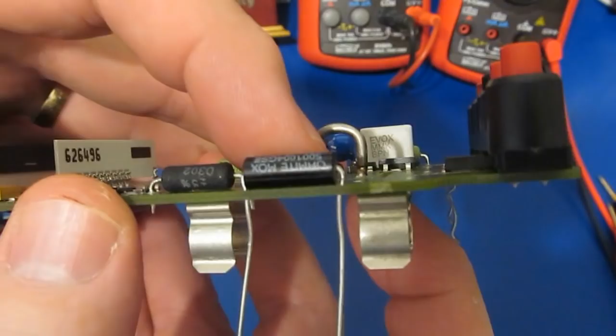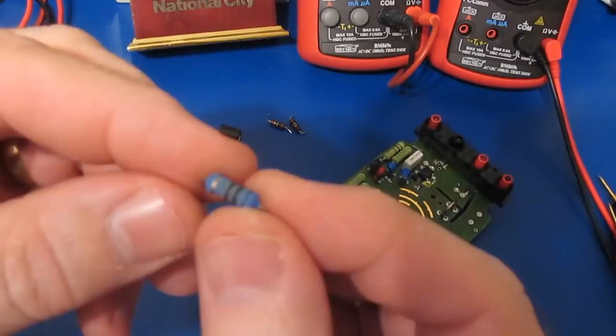If we look at the other placement again, there's no clearance issues here. The other option would be to use this device here. Again, it's a 2-watt device and it's only rated for 350 volts. This device is going to fit without any problems at all. From a fit standpoint, this is definitely our best choice.